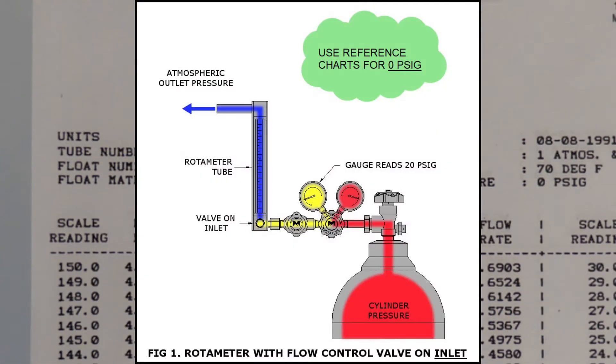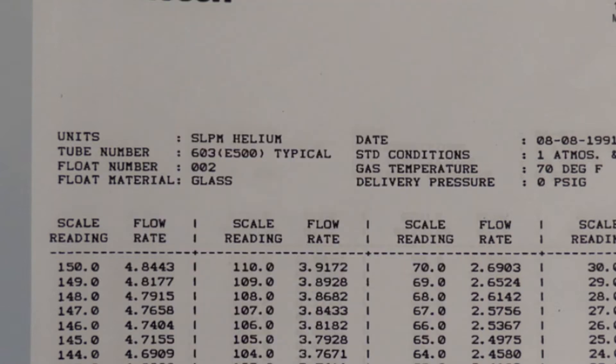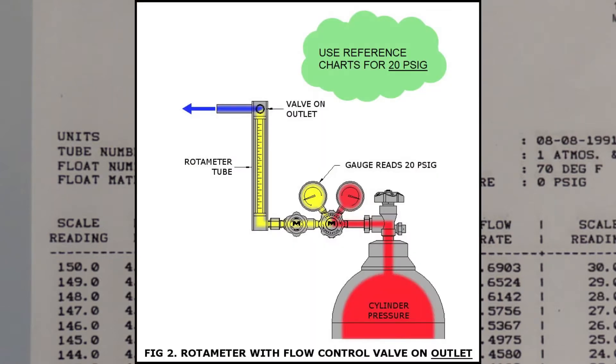The pressure that you choose is the pressure that is in the tube. Most people have the valve on the inlet with the rotometer flowing to an instrument or process at atmospheric pressure. In that case you would use the zero psi charts. If your valve is on the outlet of the rotometer, then use either a pressure correction factor or a reference chart corresponding to the pressure in the tube.